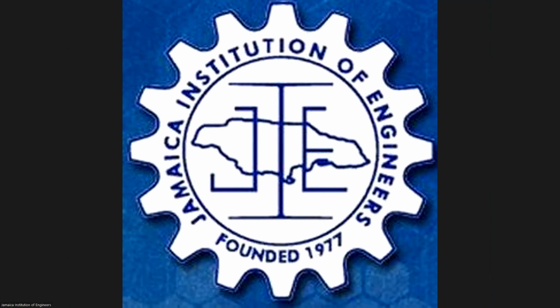What is a typical basis or the common issues that influence those red locations on the map where 50% of applications are not endorsed? Usually it's lack of water supply or lack of infrastructure to support them. So places where we have no systems available, we can't give you any water because we have nothing available in that particular area. Or where we have very little infrastructure, you're putting up 100 houses and we only have a 1/2-inch pipe in that particular area, and the 4-inch pipe is very far away, or the bigger pipes are very far away. We may say we don't have infrastructure there.